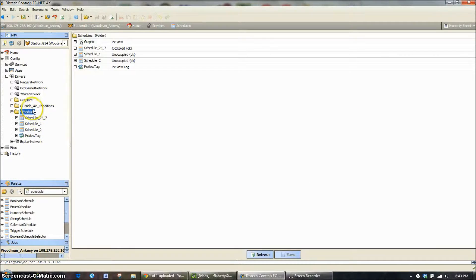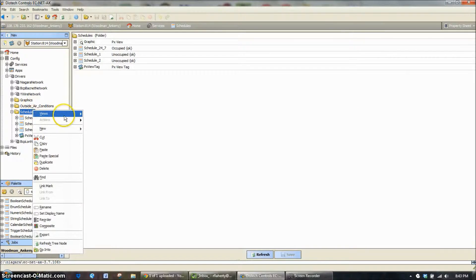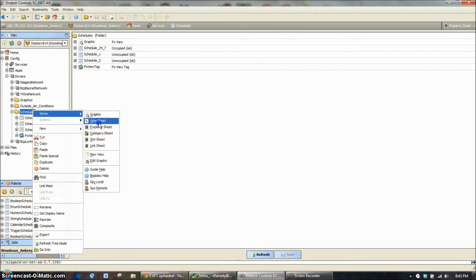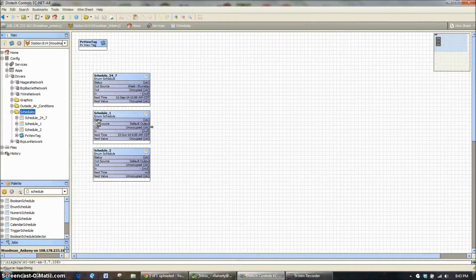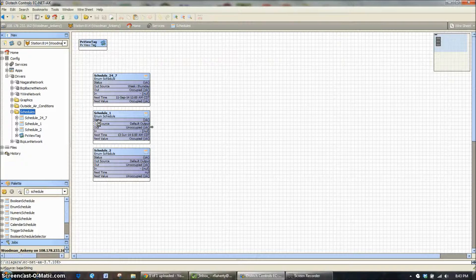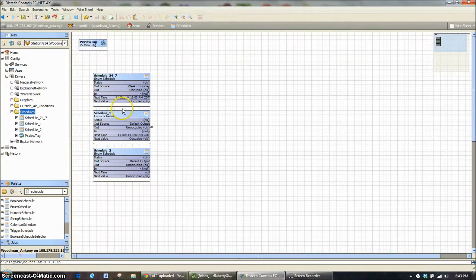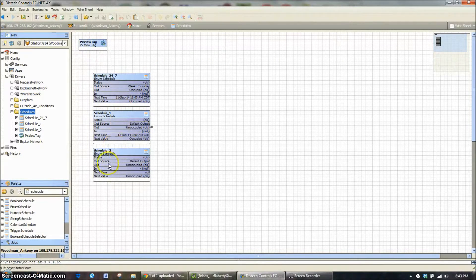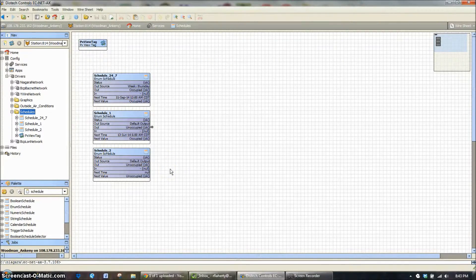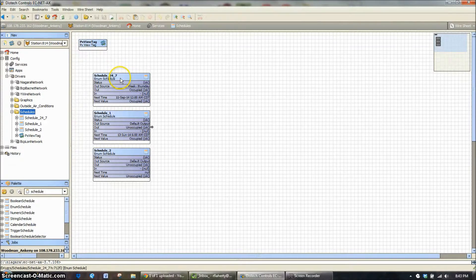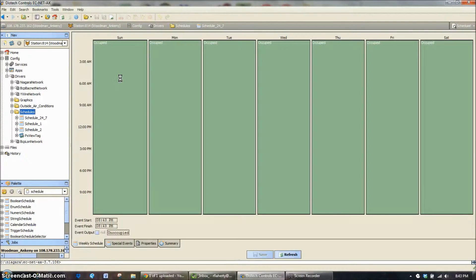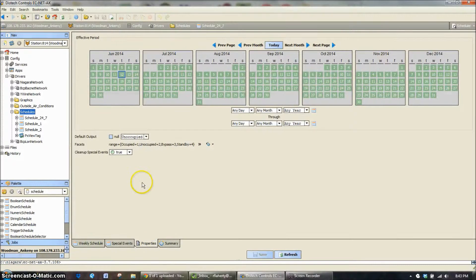So I'm going to go to the wire sheet here. On the wire sheet you're going to see the three types of schedules. The 24-7, schedule 1 and schedule 2 are all what are called enumerated schedules. And in an enumerated schedule it means it has multiple ways that it can be configured.